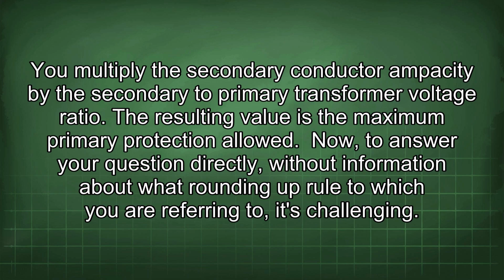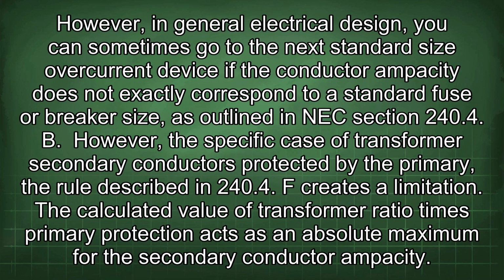Now, to answer your question directly, without information about what rounding up rule you are referring to, it's challenging. However, in general electrical design, you can sometimes go to the next standard size overcurrent device if the conductor ampacity does not exactly correspond to a standard fuse or breaker size, as outlined in NEC section 240.4(B).